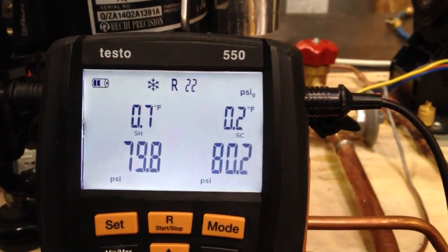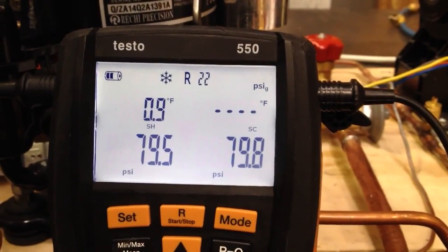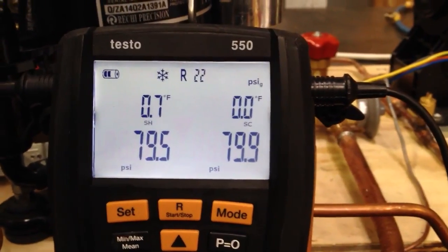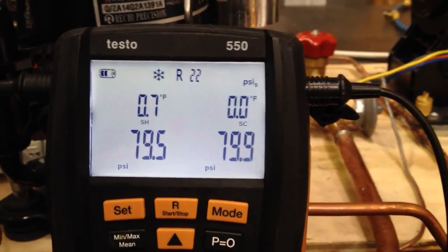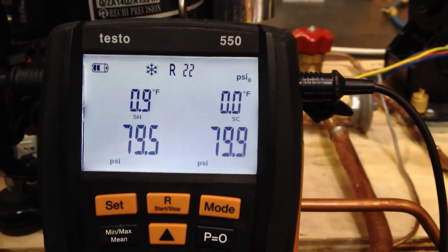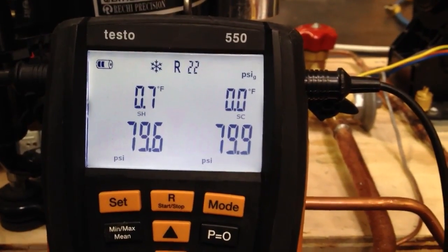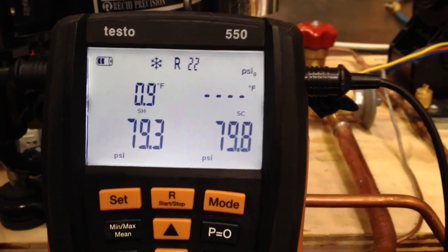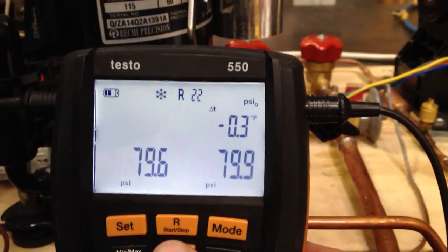A little bit closer to saturation temperature, with very minimal influence from outdoor ambient temperature on those clamp probes. You can see this thing is running right there. The reason we're seeing sub-cooling come to zero is because we're literally falling into the point where there's no superheat, no sub-cooling — it's right there. It's one tenth of a degree — less than one tenth of a degree — of being nailed on the saturation temperature.